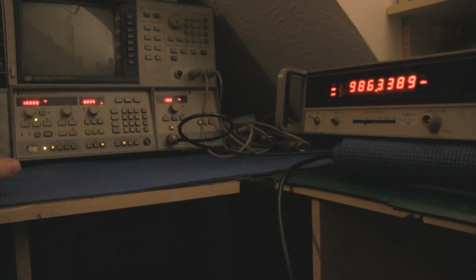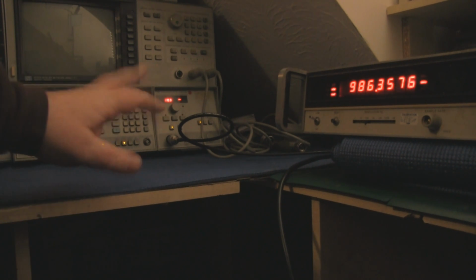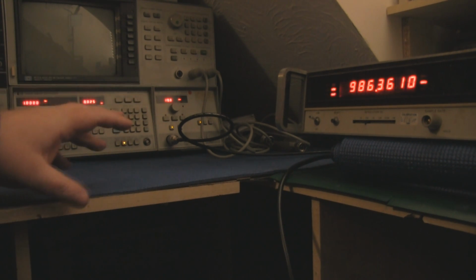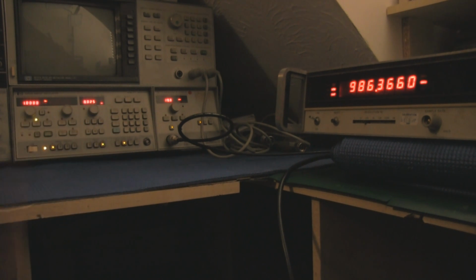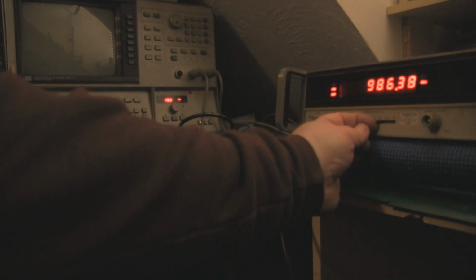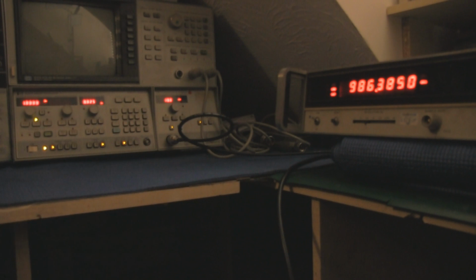Now I'm feeding in a 1 GHz signal here, and as you can see on the display, it's coming out at 986.35 MHz. Now that's a little bit out, and it's not due to the loss in the cable either. The loss in the cable wouldn't be that much, so it's a little bit out at 1 GHz. And the frequency scale on here, the resolution scale, sorry, does work really well. It latches on and engages, so we can see the resolution of that frequency scale.